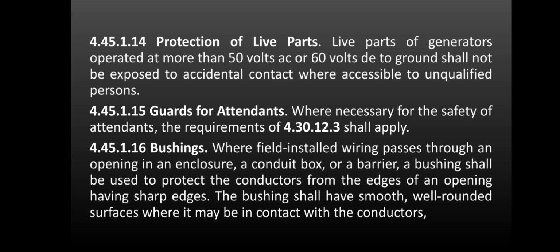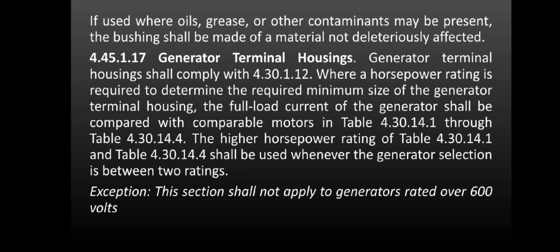Protection of live parts. Live parts of generators operated at more than 50 volts AC or 60 volts DC to ground shall not be exposed to accidental contact where accessible to unqualified persons. Guards for attendants shall be used where necessary for the safety of attendants. The requirements of 4.30.12.3 shall apply. Bushing. Where field installed wiring passes through an opening in an enclosure, a conduit box, or a barrier, a bushing shall be used to protect the conductors from the edges of an opening having sharp edges. The bushing shall have a smooth, well-rounded surface where it may be in contact with the conductors. If used where oils, grease, or other contaminants may be present, the bushing shall be made of a material not deleteriously affected.